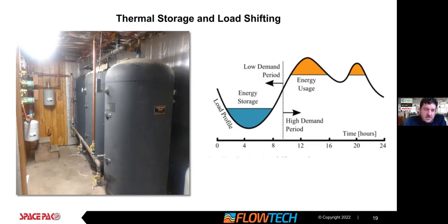This is a good example of that, maybe slightly extreme, if you will. There's 600 gallons of storage heated up at night off peak and utilized during the day when the demand is high. So utilities really like these systems, and I'm seeing this as a way that hydronics as a method will be becoming more and more mainstream as we move into electrification.